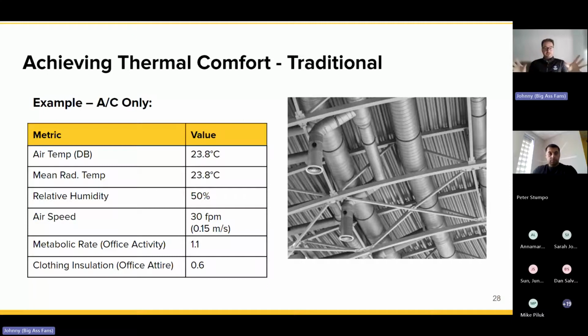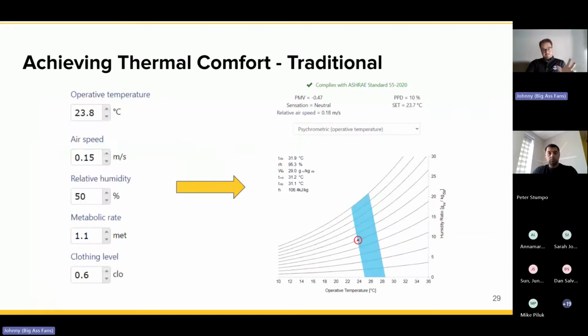So this would be like your conventional design building, no fans, ductwork, diffusers, you're dumping in cold air, you're trying to keep it comfortable. Metabolic rate and clothing level, again, is indicative of an office. So we're going to have some fun with this. Again, if you plot this on that chart, you can see that they are comfortable. The PMV is negative 0.47, and 90% of people are happy. So this technically complies, but pay attention to that set point of 23.8, that ambient temperature.